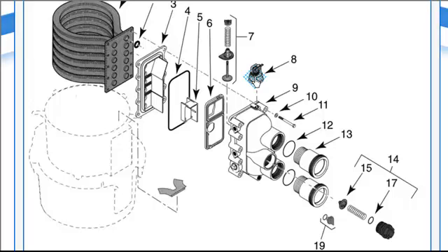Number one, to prevent the dry fire, the heater should be wired to the pool pump. Number two, the heater should constantly see water flow. Number three, if you do have bypass valves, turn off your pool pump, release the water pressure, okay? Crack one of these union nuts and pull out the drain plug and let all the water drain out.